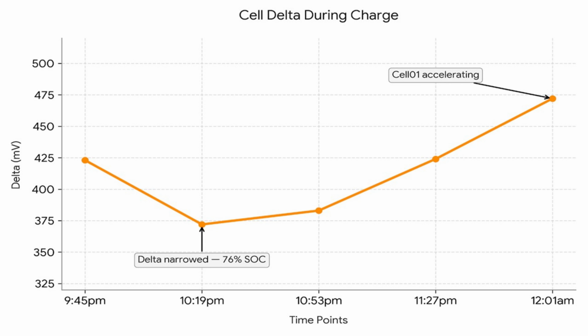The cell voltage delta, the gap between Cell01 and Cell07, briefly narrowed to 372 millivolts at 76% state of charge. Then it widened again as Cell01 accelerated toward the top of the charge curve. By midnight, Cell01 was at 3.38 volts, and the delta had reached 472 millivolts. The passive balancer requires a cell to reach 3.75 volts before it activates. Only Cell01 was approaching that level.